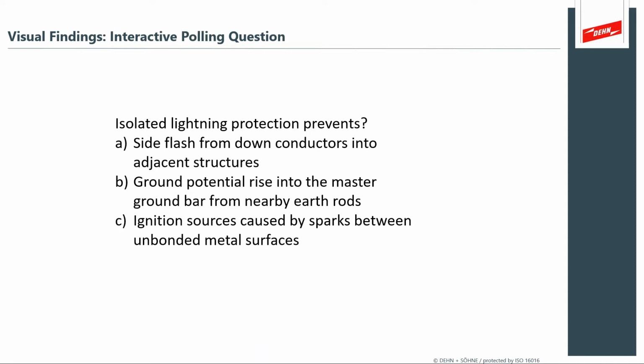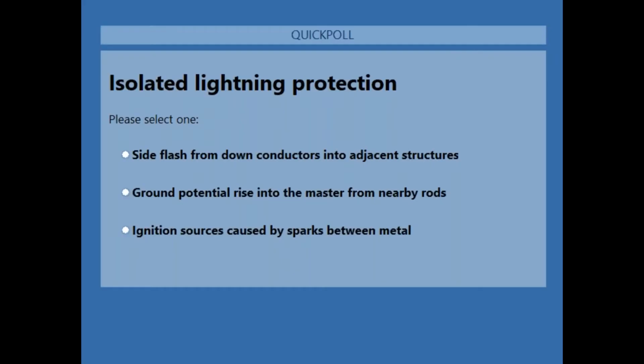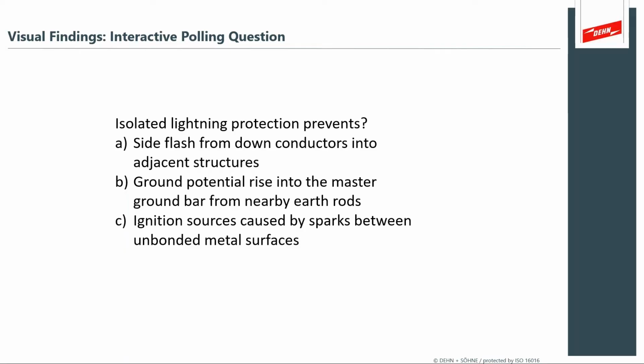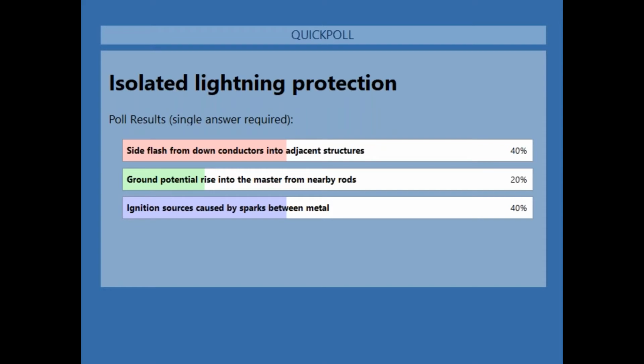So, isolated lightning protection. We've seen two conditions where we're looking at what looks like equipotential bonded lightning protection. But what does isolated lightning protection prevent? Isolated lightning protection prevents side flash from down conductors into an adjacent structure. Does it prevent ground potential rise at the master bar from other nearby earth rods? Does it prevent ignition sources from sparks between unbonded metal? What does isolated lightning protection prevent? So when you're at a site and you see these types of systems, what was it there for? It helps you understand the value of the system. The polling results are sort of a mix between side flash and sparks, which, again, you like my trick questions. It does all three of these things. It's just, again, understanding what the customer's perspective should be.